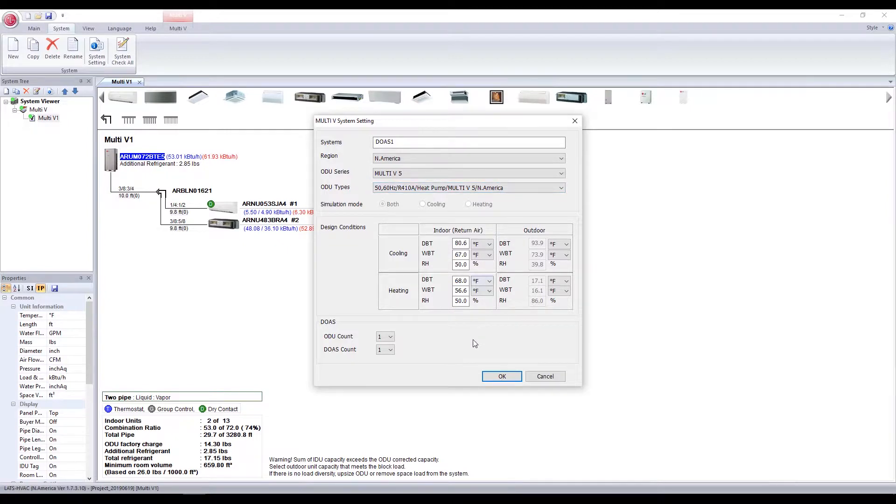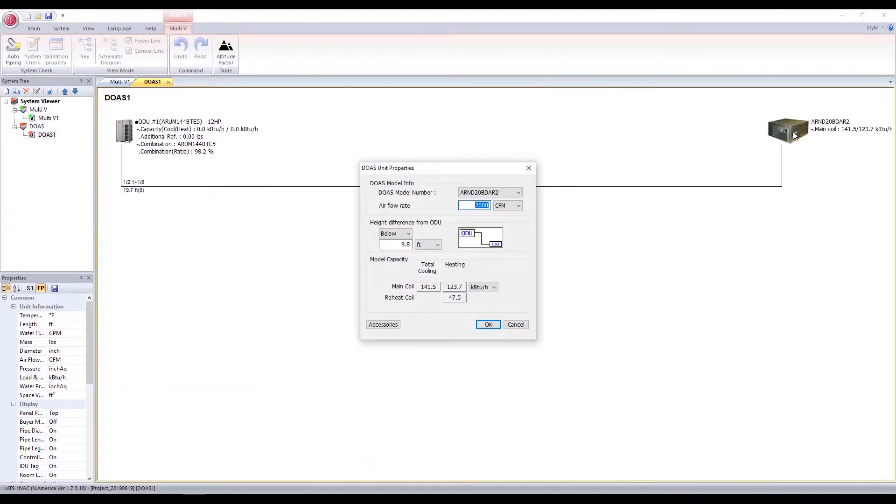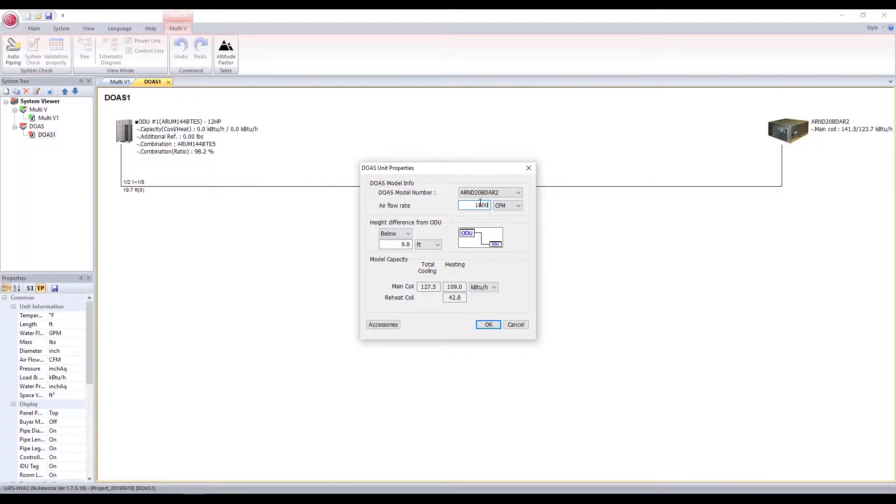You can select the DOAS unit by double-clicking the icon and choosing from the model numbers. You can change the CFM value to be in the recommended range of 400 to 2000 CFM. Add accessories as necessary.